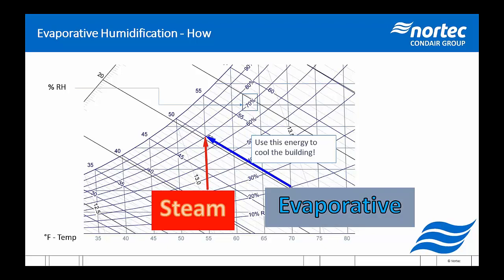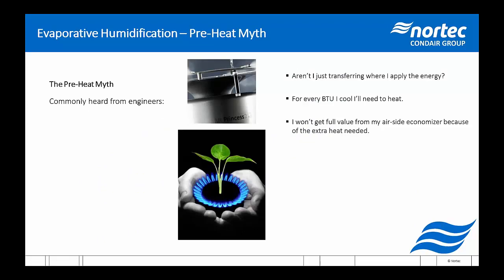In a little bit more depth, which I'll get into in a minute, a lot of people say, look at this line here, this blue line. If I'm cooling, I'm going to have to heat. I'm going to have to do extra heat. So now I'm going to get a little bit into the preheat energy myth, as I call it. And what I hear all the time, and I don't blame people because this is what I said when I first heard about this style of humidification and cooling, is: if I'm humidifying with an evaporative humidifier, aren't I just transferring the energy from the humidifier to the airstream? Yes, but you don't necessarily have to apply any more energy to the airstream.